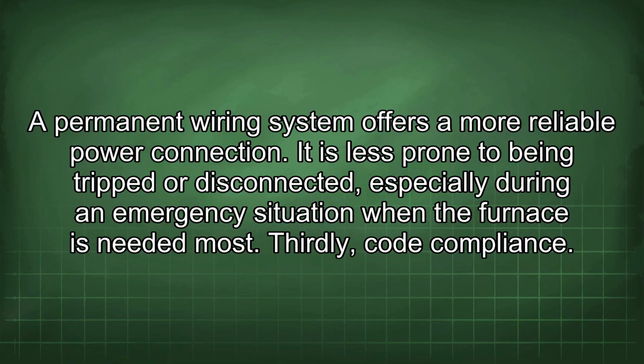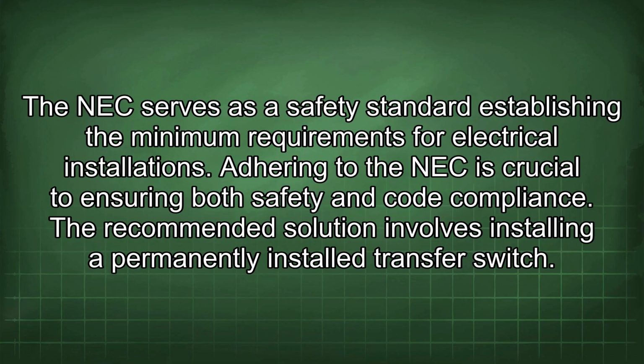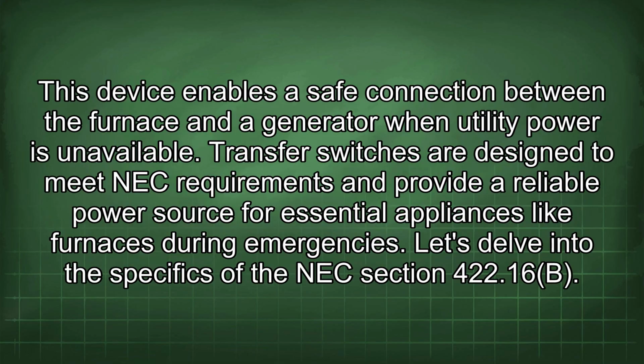Thirdly, code compliance. The NEC serves as a safety standard establishing the minimum requirements for electrical installations. Adhering to the NEC is crucial to ensuring both safety and code compliance. The recommended solution involves installing a permanently installed transfer switch. This device enables a safe connection between the furnace and a generator when utility power is unavailable. Transfer switches are designed to meet NEC requirements and provide a reliable power source for essential appliances like furnaces during emergencies.